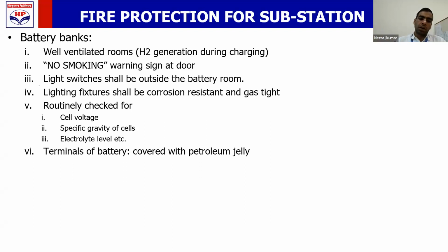If your battery cell electrolyte level is not at the right level, or its internal resistance is increasing, then it poses a different hazard. So you should routinely check cell voltage, specific gravity, and electrolyte level in your batteries. This should be done on a consistent, regular basis. Terminals of batteries shall be provided with petroleum jelly. This is primarily to avoid corrosion and opening of terminals because of the corrosion.